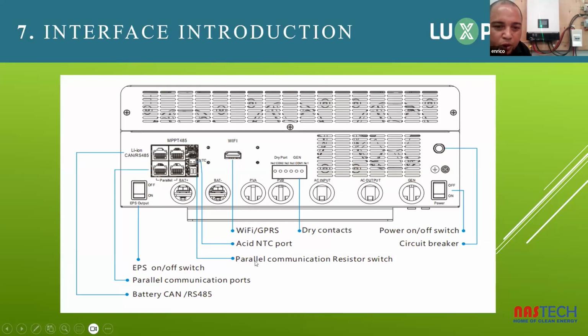Please also keep in mind when doing the parallel communication, resistor switches need to be up. This resistor dip switch coloring on the plastic is either red or blue. The red is the older version, the blue is the newer version. This is the dry port contact for your generator input.